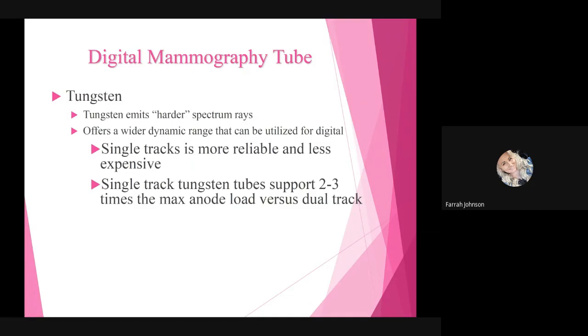Then for digital mammography tubes, we have tungsten targets. Know that tungsten is going to emit a harder spectrum, meaning a more homogeneous beam, meaning that the energy levels of your beam are not going to vary. If you set 20 kVp, your beam should have a majority of 20 kVp X-rays. With tungsten targets, they do offer a wider dynamic range that can be utilized for digital. Note that single tracks are more reliable and less expensive. Single track tungsten tubes support 2 to 3 times the max anode load versus a dual track.